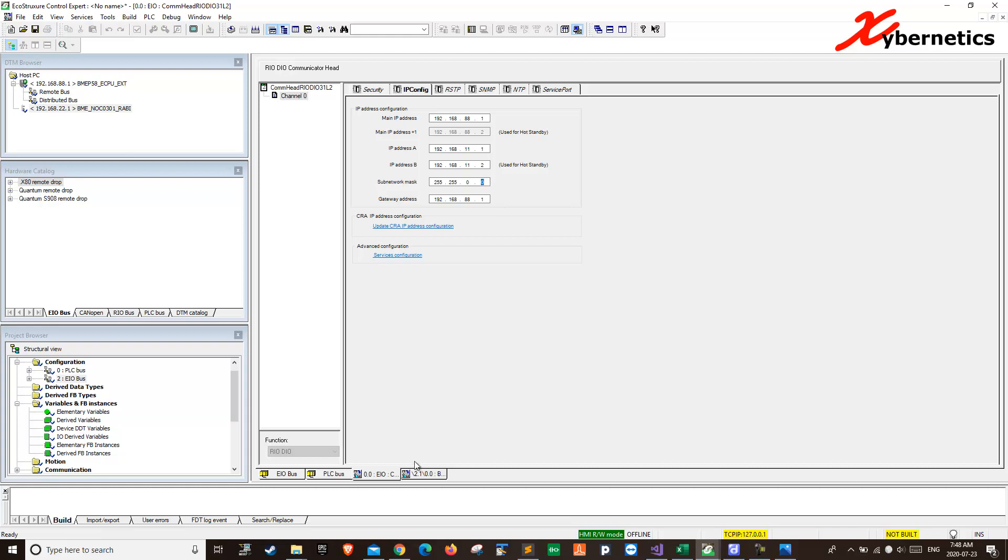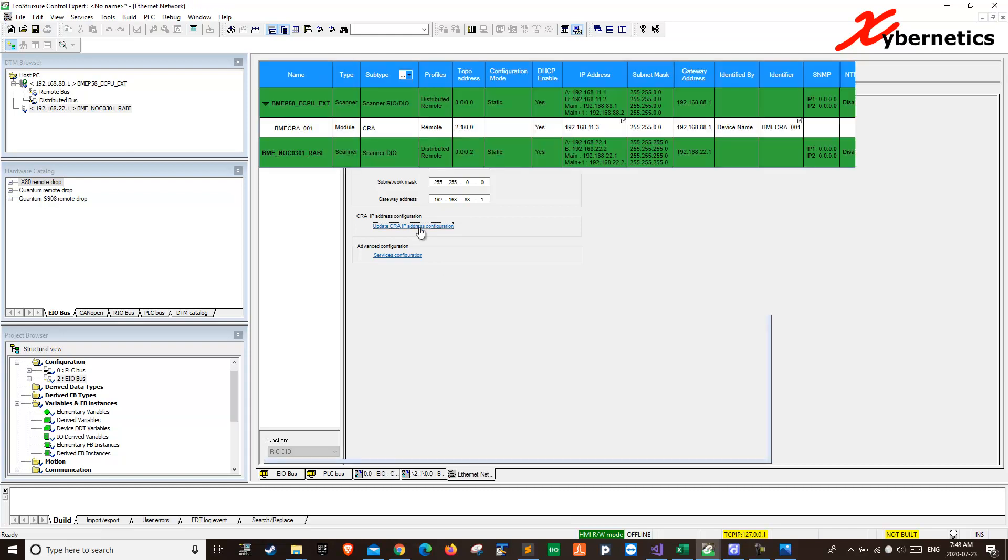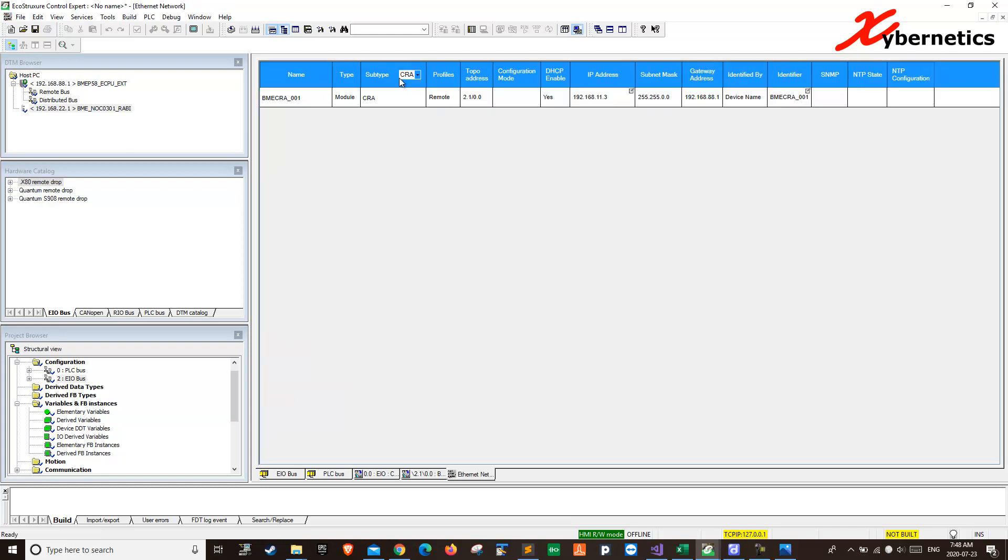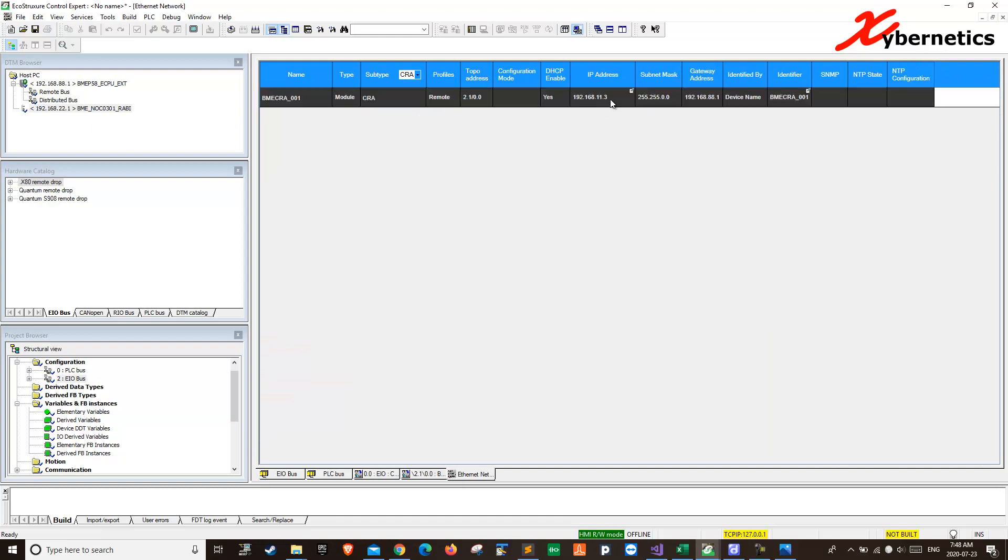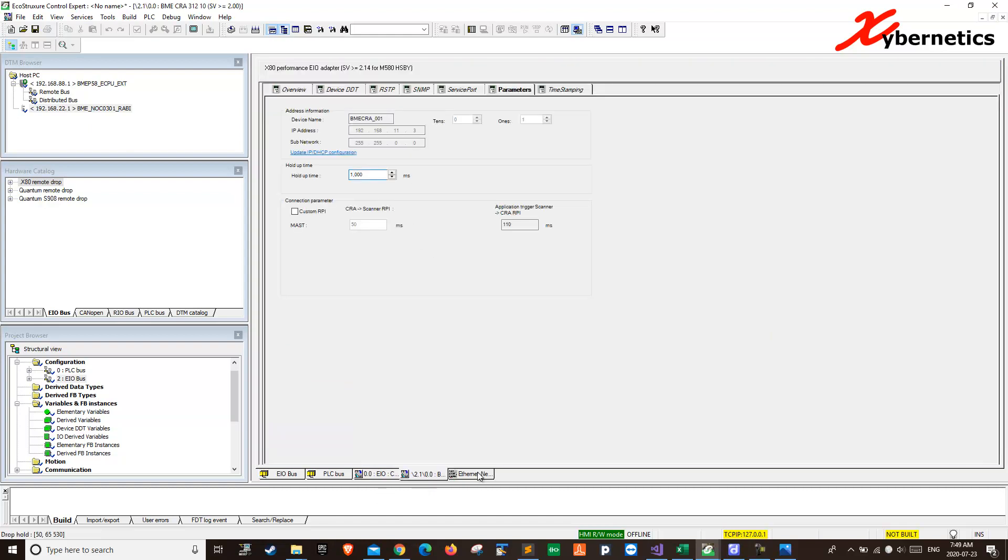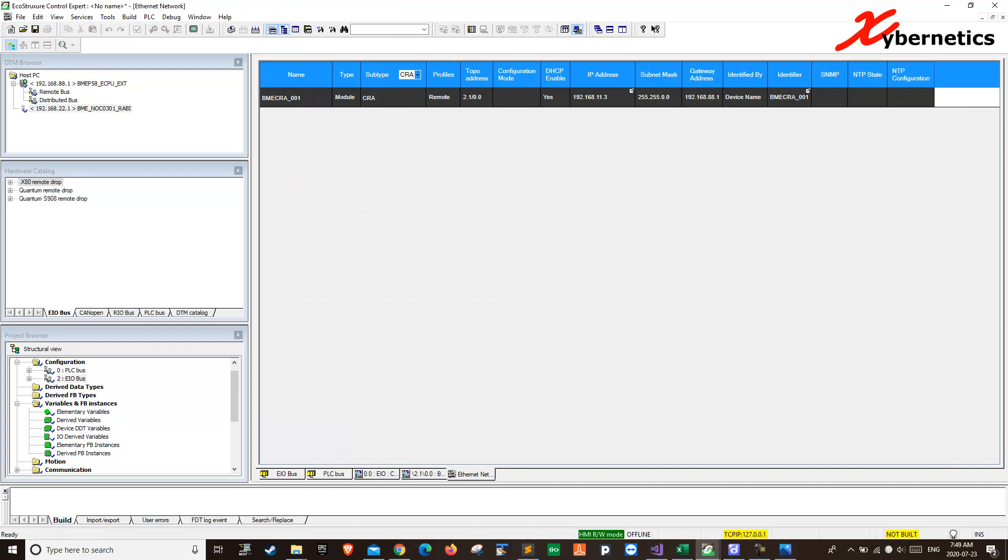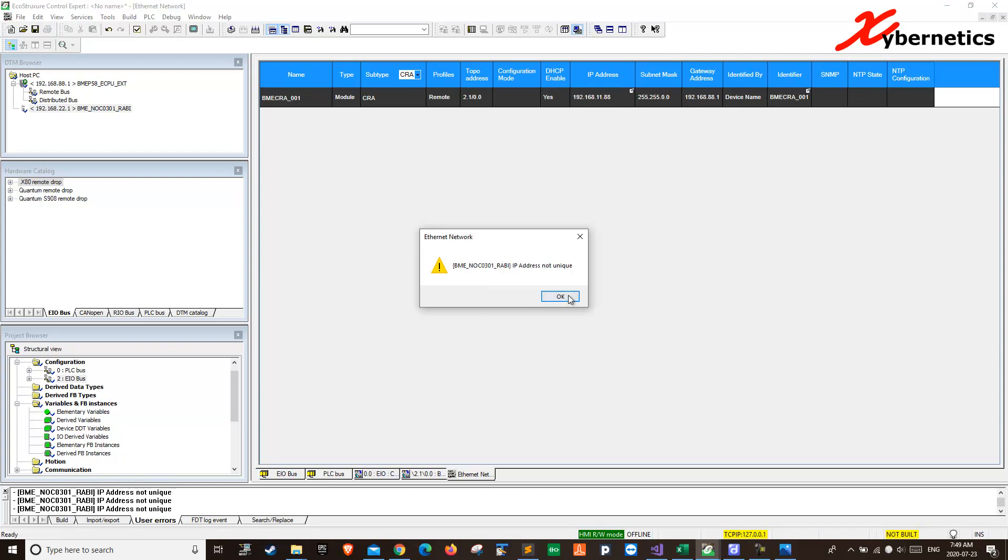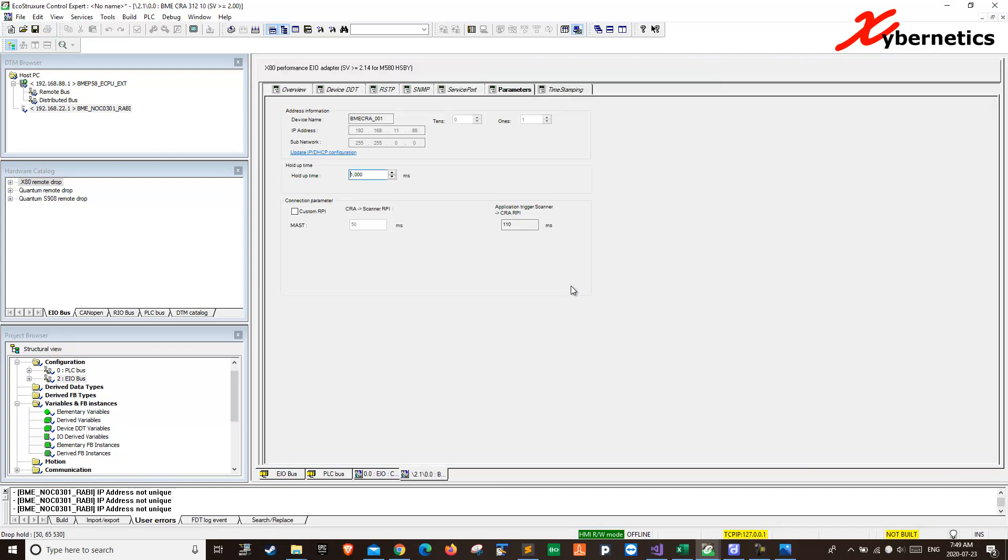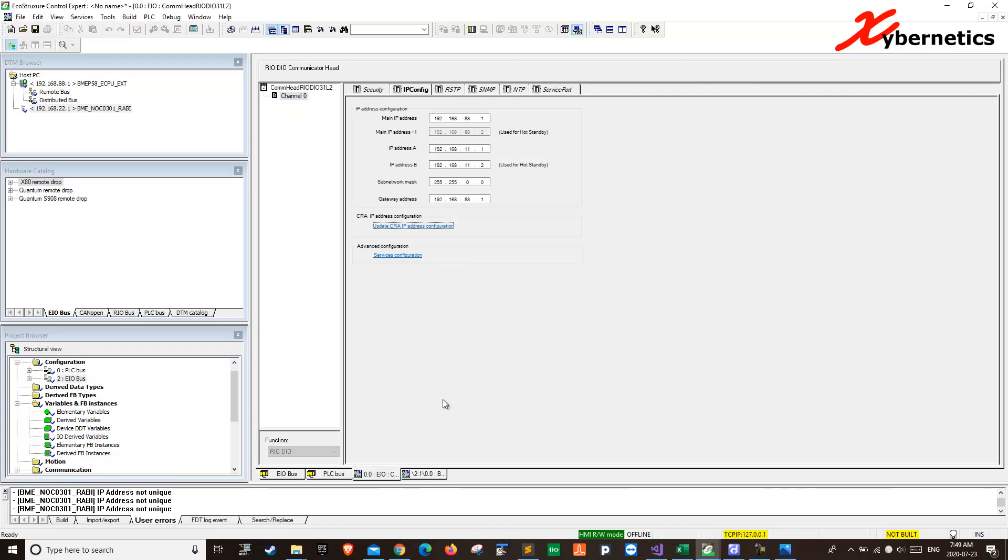So you can choose anywhere from three all the way up to 254. I think 255 is the broadcast address. You can't really use it. Dot one is not, dot two is actually being occupied by the main PLC itself. So, the way to change that IP address would be if you go to update CRA IP address configuration, click on this guy here, and you can see that it's dot three here, right? Similar to what you have here, dot three. So you do it by going in here, click this guy here and say, you want to call it 88 hit enter, save it, validate it.